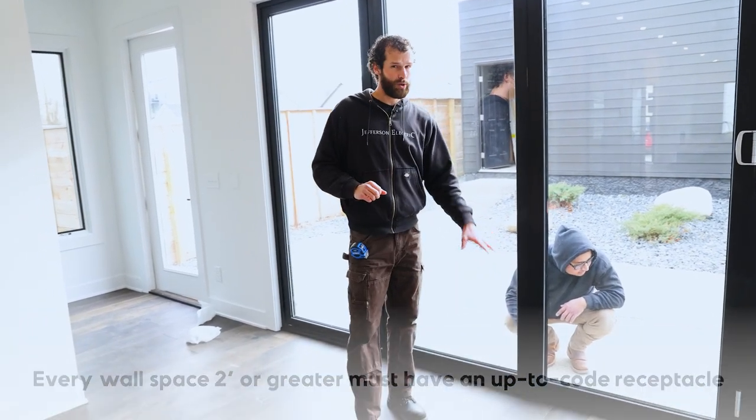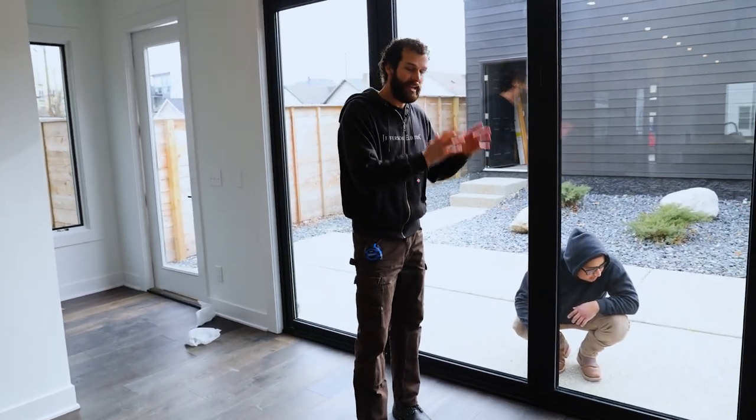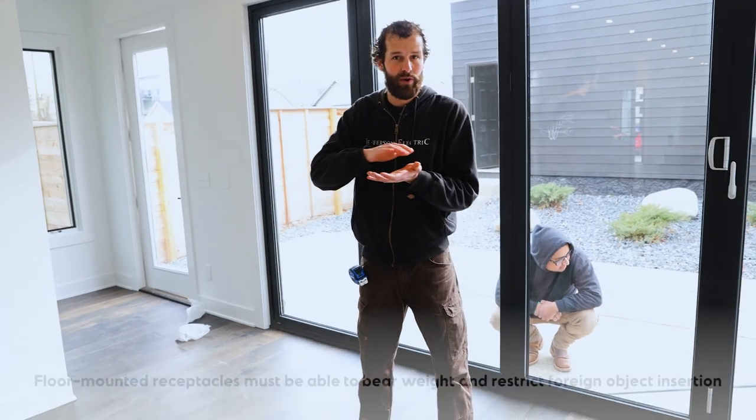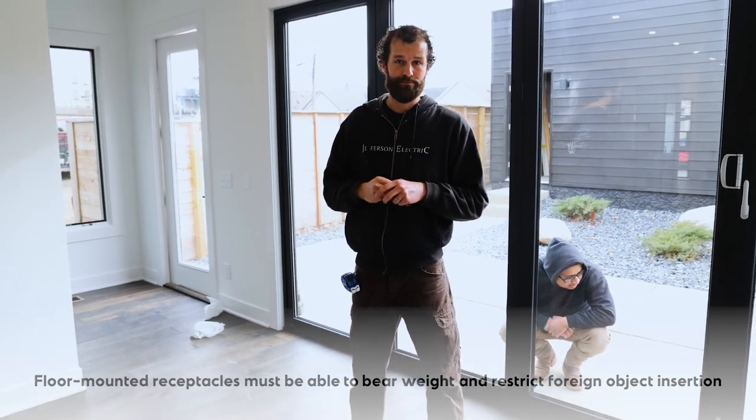Even if this were poured concrete, there would have to be provisions prior to pouring the slab for an in-concrete floor receptacle. Now, that floor receptacle must be listed and rated for that purpose. A floor receptacle is very different than a wall receptacle. The cost is about $45 higher per unit, and that's because it has to have a floor-rated cover — something able to bear weight and prevent the insertion of foreign objects, whether those are liquids, children's fingers, toys, furniture legs — the cover must be able to protect the receptacle from those foreign objects.